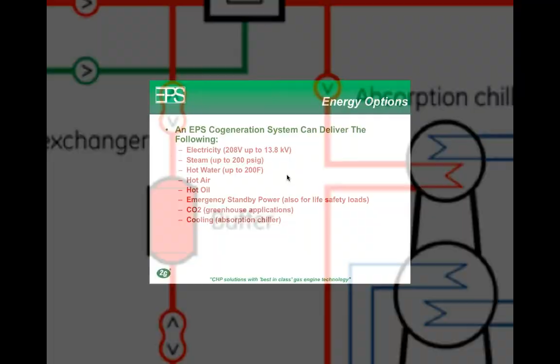Now, it's not only hot water and electricity that a cogeneration system can provide. If you look at electricity, we typically see electricity being delivered at voltages for the smallest units. We can go to 208 volt as the generation voltage. The highest that I've seen for our types of systems is about 13.8 kV as the generator voltage. Most of the applications in Ontario would see generators below 2 megawatts run at 600 volts and larger ones at 4160 volts. If you happen to export power into the grid, then this voltage could be increased to 13.8, 27 or 44 kV as required for the grid that you're connecting to.